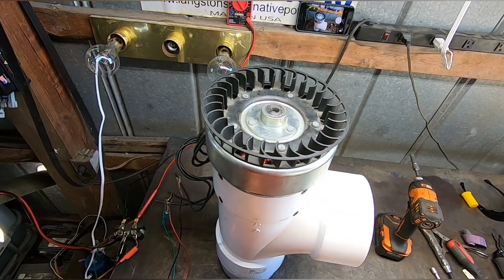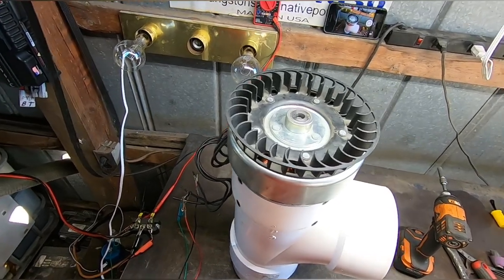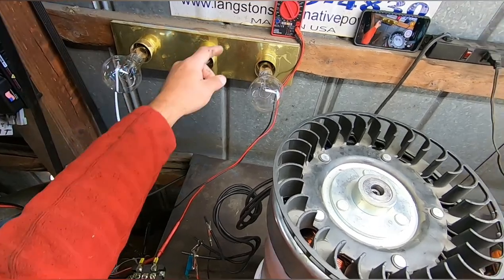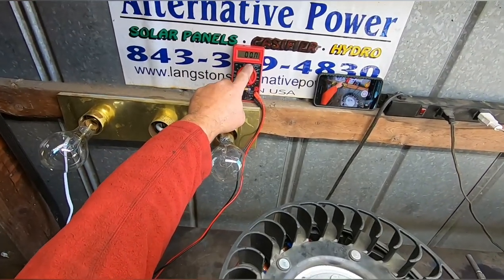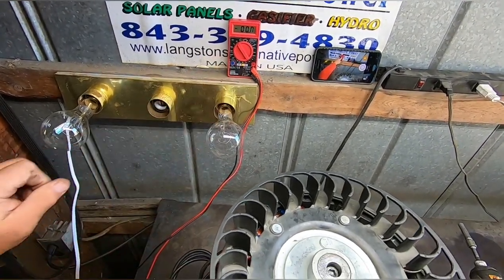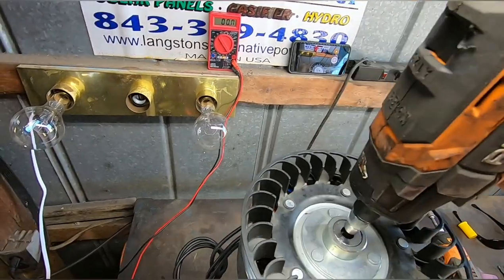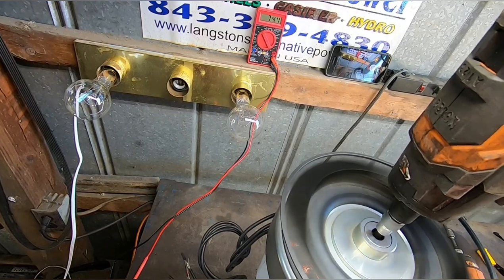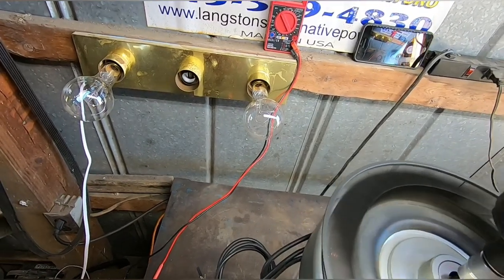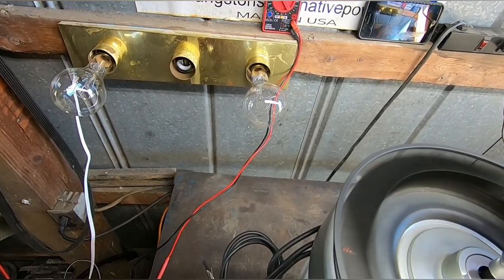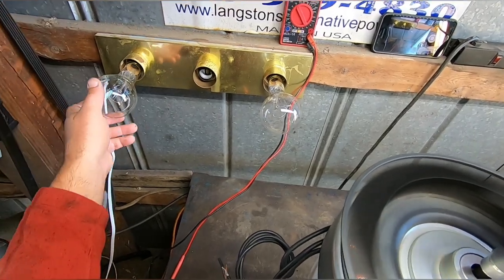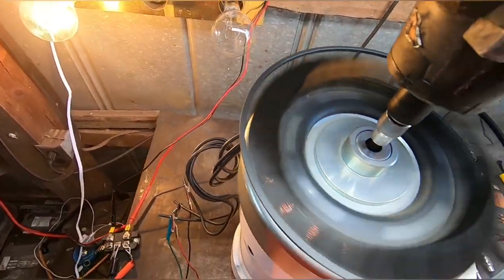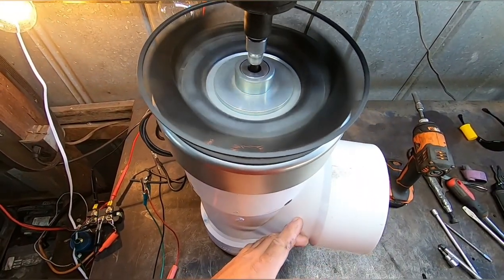Okay, now we're going to check and see if this thing's putting out any power. To start with we're going to do an open circuit voltage test. Let's see here, nothing. All right, we're gonna spin this baby up. At 120 volts. Let me check it. About 99 there. Looks like everything's working good.